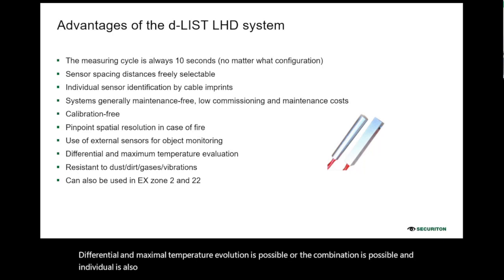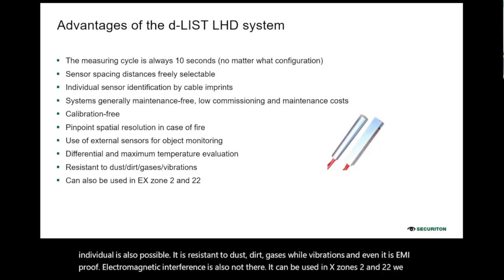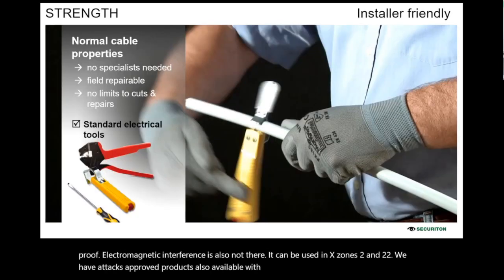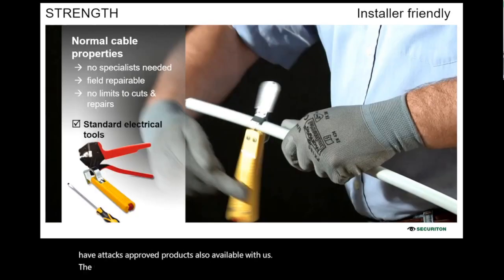It is resistant to dust, dirt, gases, and vibrations, and it is even EMI proof. Electromagnetic interference is also not an issue. It can be used in Ex zones 2 and 22. We have ATEX approved products also available. The crimping tools are available. These tools are very installer friendly, specifically meant for these kinds of cables. No specialists are needed. You can cut these cables on site and repair these cables on site. There are no limits to cutting and repairs in our cables.